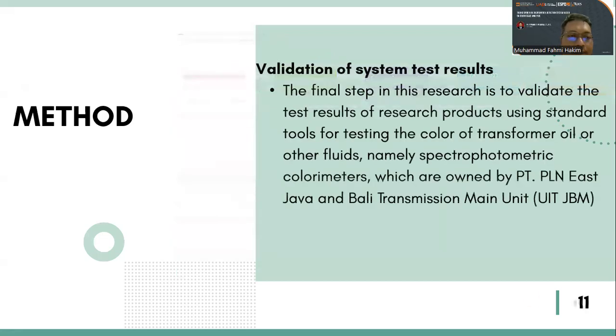And then the final step in the method is to validate the test result of the research product using standard tools for testing the color of transformer oil or other fluids, namely spectrophotometric colorimeters, which are owned by PT PLN East Java and Bali Transmission Main Unit, or UIT JBM.